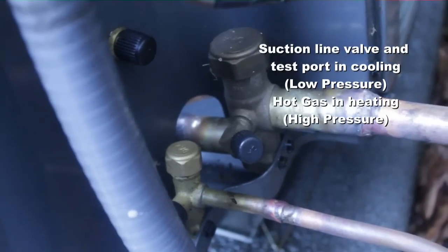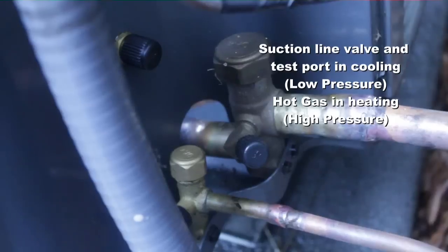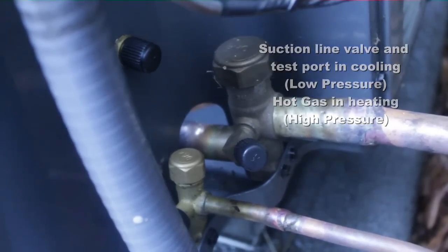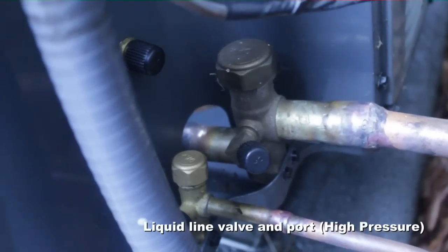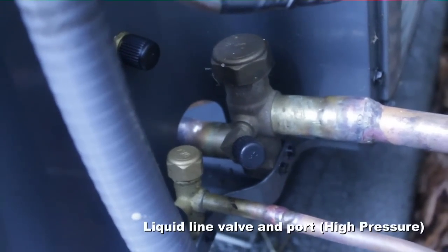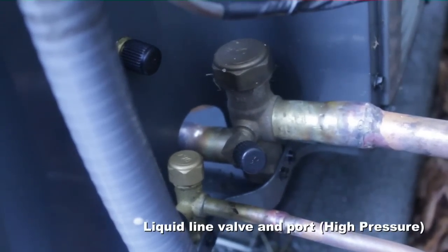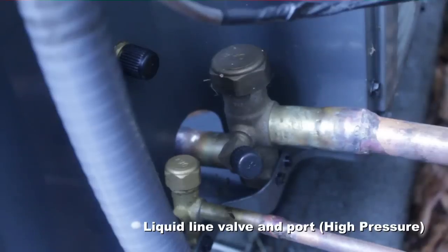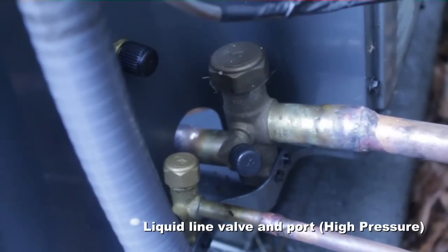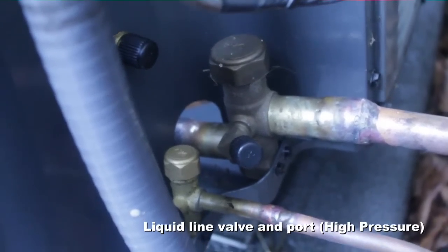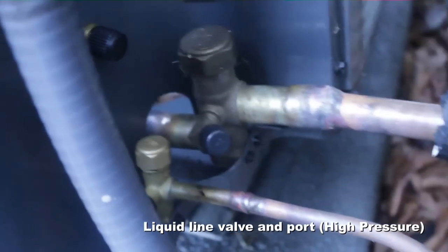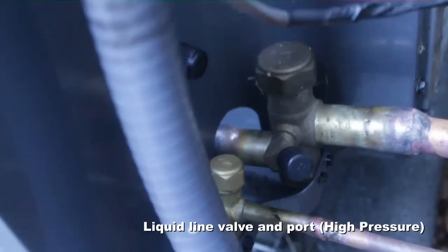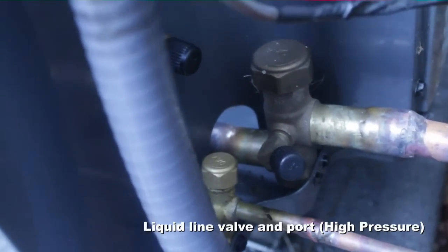In air conditioning, that is where vapor comes back to the heat pump from the evaporator as a cool vapor. On the bottom we have our liquid line. It is actually the liquid line in both cooling and heating. In cooling, the refrigerant circulates through the condenser outside, condenses to liquid, and flows to the evaporator through this line.